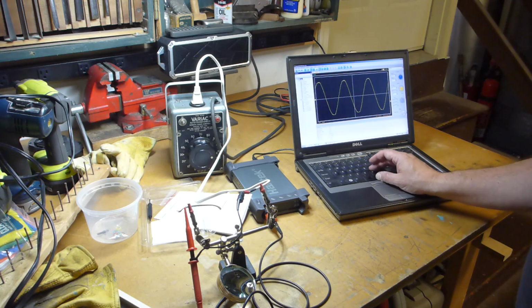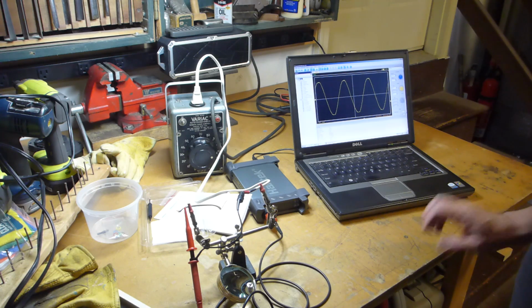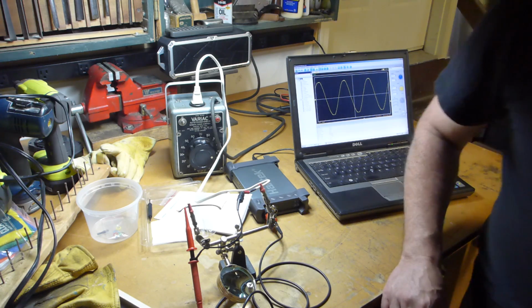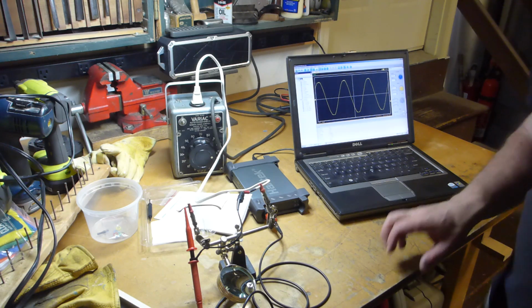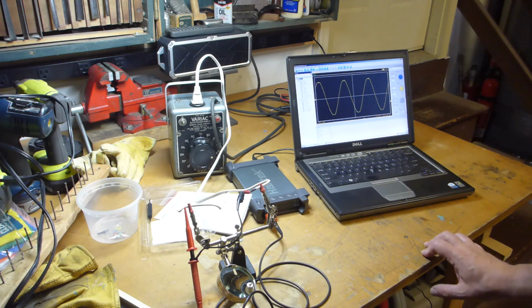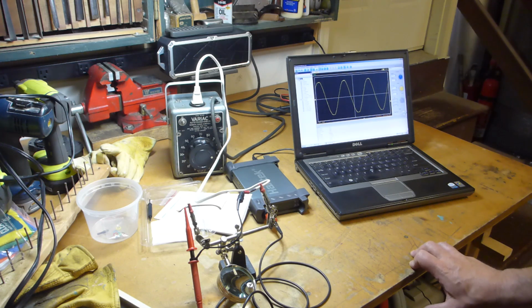But cool thing is I am now able to troubleshoot up to house current, 110 volts, and shouldn't be a problem going on up to 240. So anything I'll ever need to deal with around here, which will be cool because I have some inverters and things like that I'd like to play with and see what their signals end up looking like. So I'm in business as far as that's concerned.